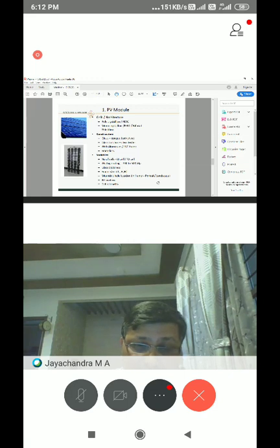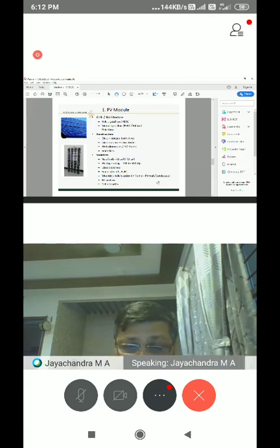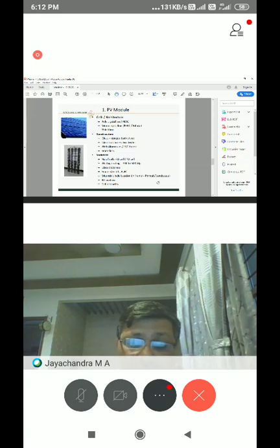I think in some cases even 2.2 mm is also there. Glass thickness, double glass, frame sizes, that is length, breadth, and height. These are variabilities I am telling because these are very much clearly to be identified before we start with any of the system design. Frame size L, B, H, because it depends on the structure. Even H, the height of the module, for the clamping decisions, and the height decisions to allow the gap between the sheet and the module. So these variabilities are there in different makes of the modules and different sizes of the module.